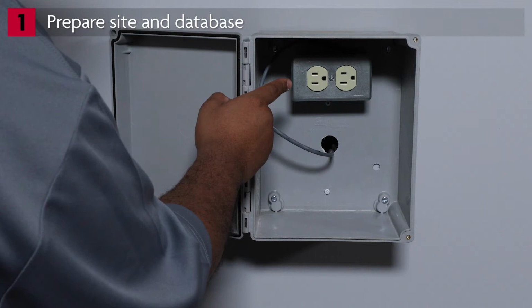The maximum distance of this wiring is 300 feet using 14-gauge 2-conductor solid wire. For outdoor installations, the dedicated outlet must be inside a weatherproof NEMA 4 electrical enclosure. Check for appropriate grounding that meets the requirements of local and national electrical codes.